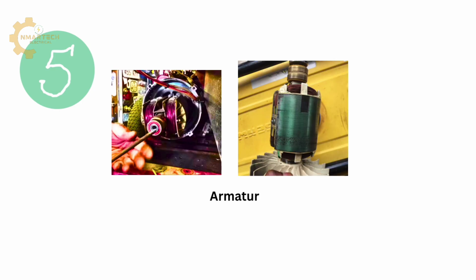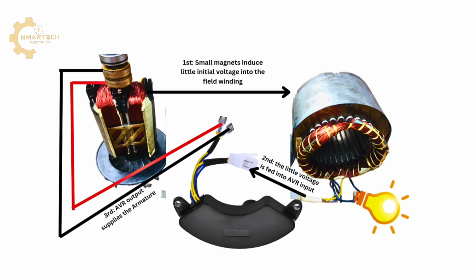Armature. An armature is the electromagnet of a generator. The armature coil receives DC voltage from the AVR. The image on the screen shows how electricity is generated. The armature plays the first role of inducing small voltage into the stator. The stator, through its exciter windings, resends the voltage in a rectified DC form back to the armature coil through the AVR and brush. With this DC voltage, the armature becomes a bigger electromagnet that can induce bigger AC voltage, which the coil sends out to the socket.